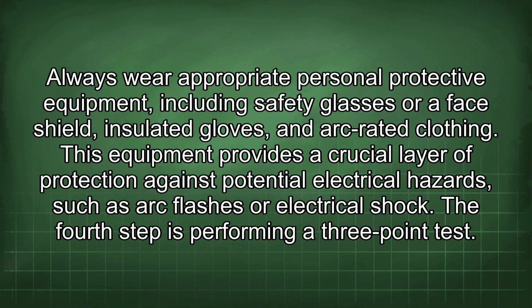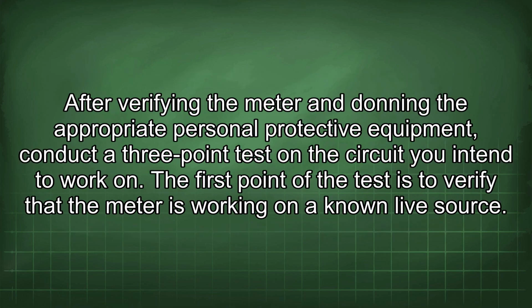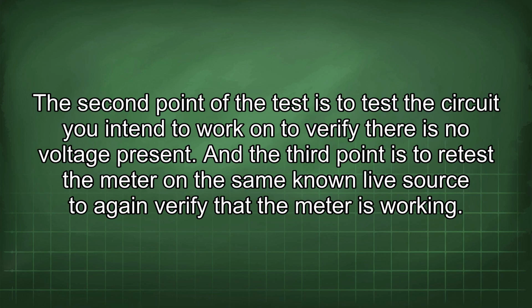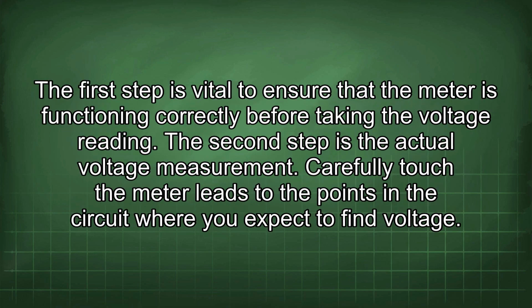The fourth step is performing a three-point test. After verifying the meter and donning the appropriate personal protective equipment, conduct a three-point test on the circuit you intend to work on. The first point of the test is to verify that the meter is working on a known live source. The second point of the test is to test the circuit you intend to work on to verify there is no voltage present. And the third point is to retest the meter on the same known live source to again verify that the meter is working.